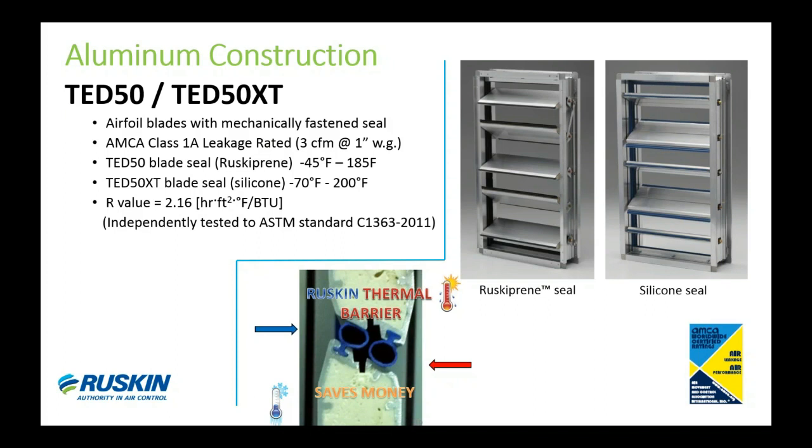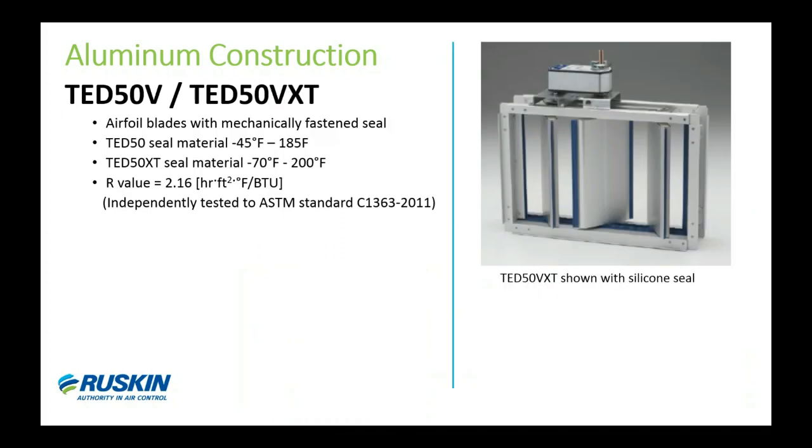The thermal brake is in what we call a neutral zone between the two twin seals, and this eliminates a thermal path for hot or cold air transfer, helping reduce energy costs. The R-value for these models is 2.16, based on a three-foot square panel of closed blades. This was recently tested by Intertek to the standard test method for thermal performance of building materials and envelope assemblies. We also have vertical blade versions of both models, called the TED50V and the TED50VXT.